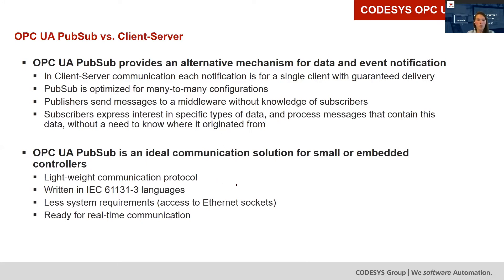Subscribers just define a certain configuration and a certain dataset, and then they can communicate with each other. The big advantage of OPC UA PubSub is that it is an ideal communication for small and embedded controllers, because in comparison to client-server, it is a really lightweight communication protocol. It is also written in IEC 61131 language, so it has the same advantage as other IIoT libraries or Fieldbus stacks — you can bring it to any Codesys controller. It has quite low system requirements; at minimum you just need access to Ethernet sockets via the SysSockets runtime component.